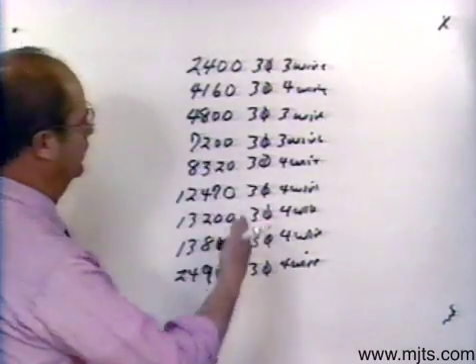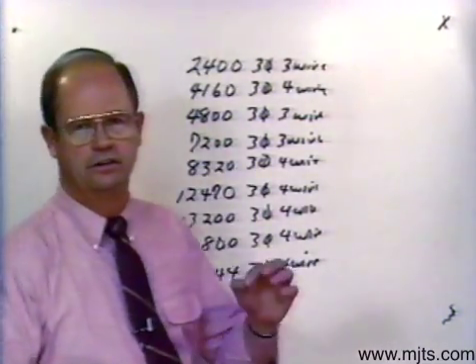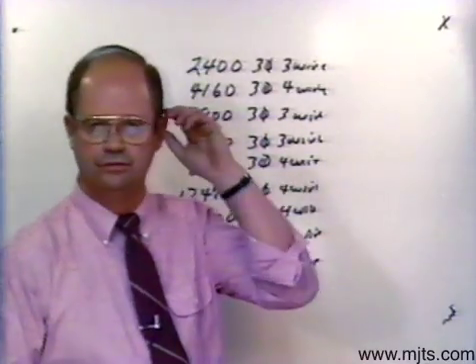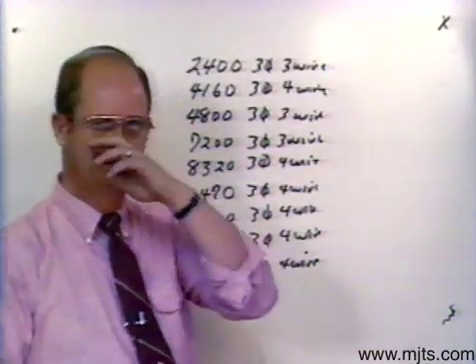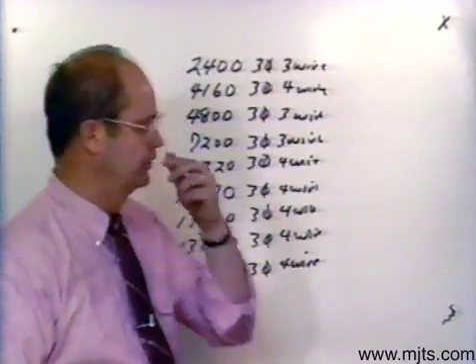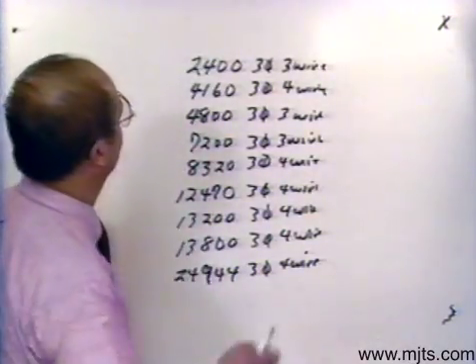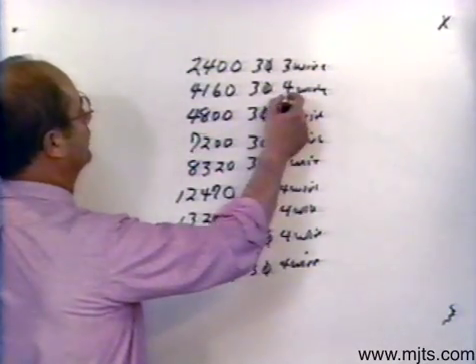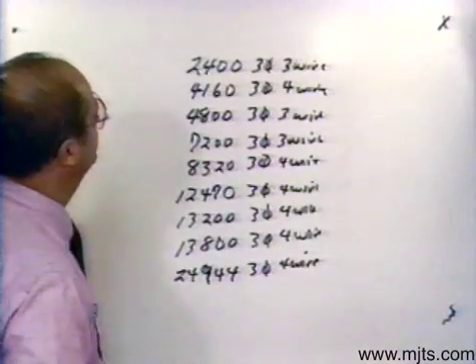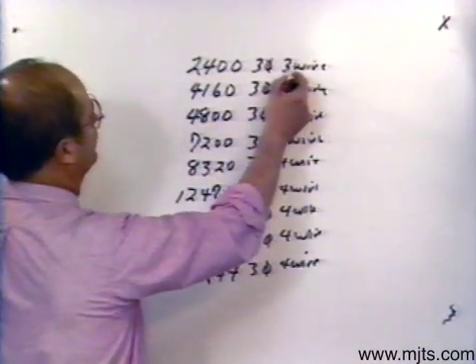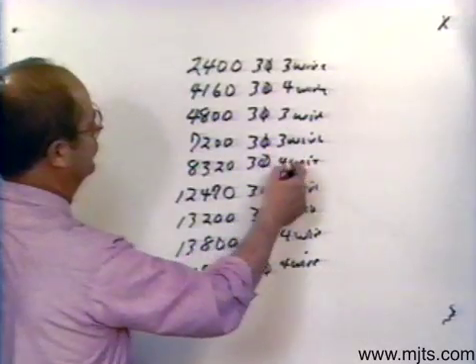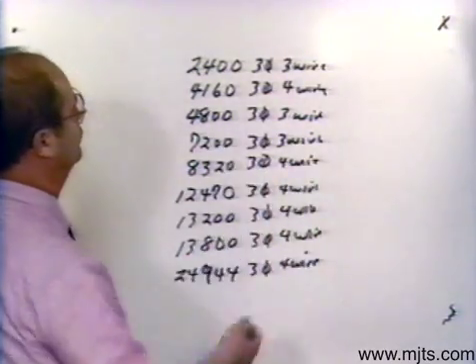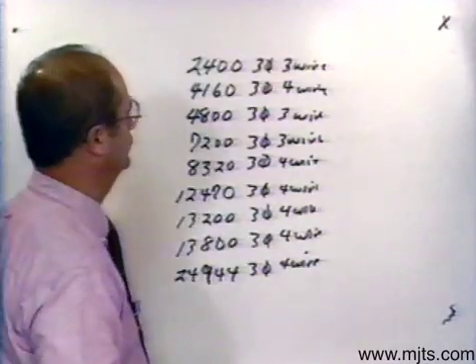Now, what I've got here is a list of some system voltages. And if you'll remember that I mentioned three-wire is delta and four-wire is Y. And if you go down the line like here we've got three, four, three, three, four, four, four. Most of your distribution systems are going to be four-wire.